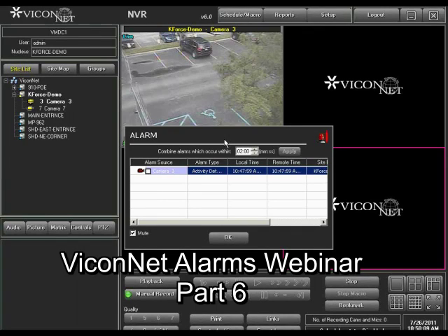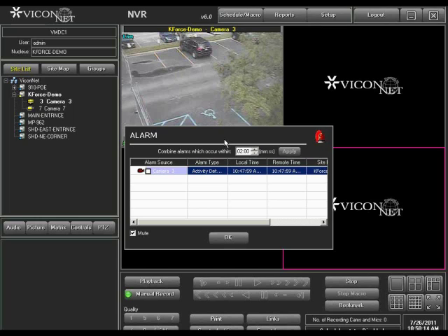To utilize this command with an alarm sequence, one needs to create a macro that will display particular cameras based on different alarm situations. Once the different macros are created, each displaying different cameras for different alarms, all that is left is to trigger those macros at the correct time. The device where the alarm occurs will be the trigger. The macro that runs because of the alarm will use the remote macro command and select the viewing machine's respective macro. This effectively will cause the correct cameras to be displayed once the alarm occurs.